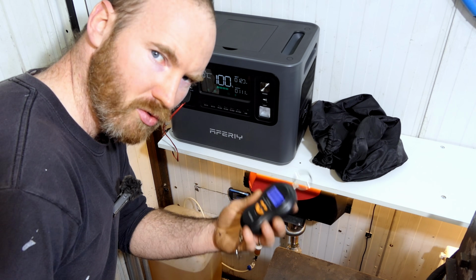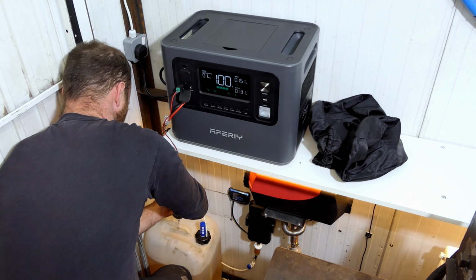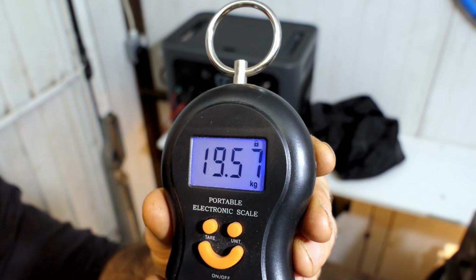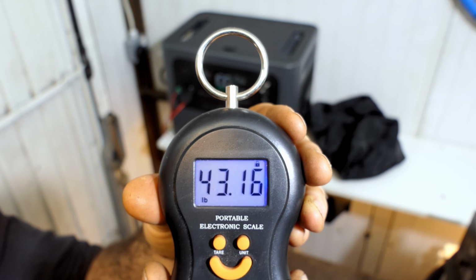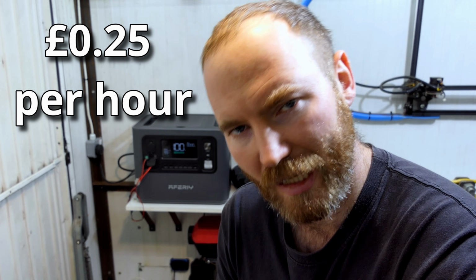So 2 hours in total, how much fuel did we use? We're now down to 19.57 kilograms, or otherwise 43.16 pounds. So with a little help from ChatGPT, the difference in weight is 0.76 kilograms of kerosene, which works out to be 0.95 litres used over a 2 hour period. In total, that was just over 9 kilowatt hours of energy, or 30,967 BTUs. That means the diesel heater itself was averaging 4.54 kilowatt hours. So again, that is not an 8 kilowatt unit, which is what it was advertised as. But because we're wasting so much heat outside, it's hard to know what the efficiency actually is.